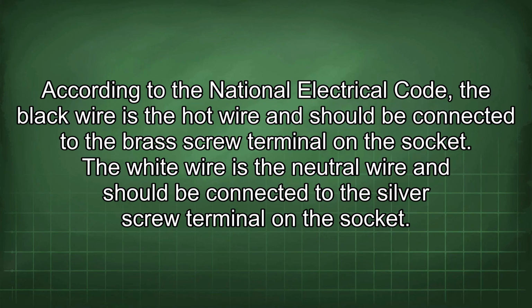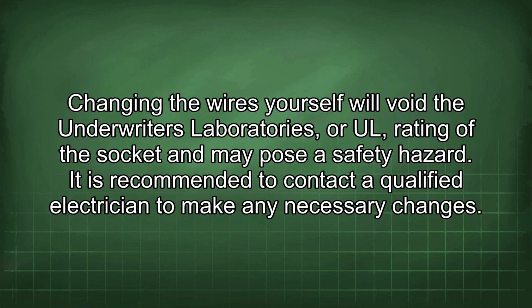According to the National Electrical Code, the black wire is the hot wire and should be connected to the brass screw terminal on the socket. The white wire is the neutral wire and should be connected to the silver screw terminal on the socket. Changing the wires yourself will void the Underwriters Laboratories (UL) rating of the socket and may pose a safety hazard. It is recommended to contact a qualified electrician to make any necessary changes.